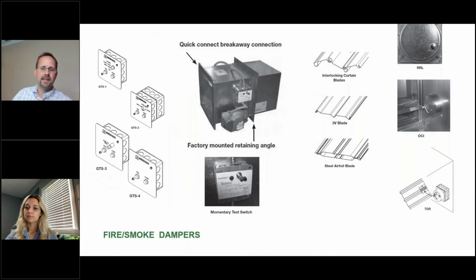And then again, smoke dampers have quite a few different options, and I'm going to run through these really quickly. First of all is the blade type. There are grooved and airfoil blades, and the big difference is that the grooved type blades are a lot cheaper. So if you don't say one way or the other, they're the ones a contractor is going to purchase. The airfoil blades have a significantly reduced pressure drop. So in any medium pressure system, or even big return air systems that have a lot of smoke dampers in them, I would definitely recommend the airfoil blade, because that pressure drop can add up over a number of dampers and create issues with your system.